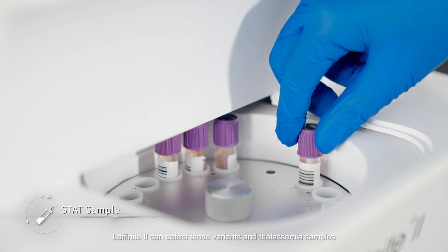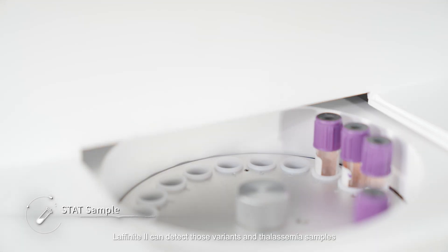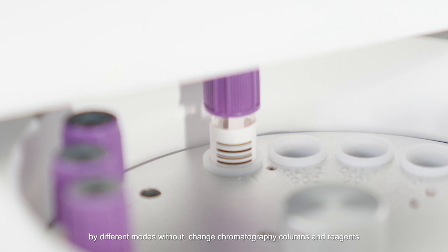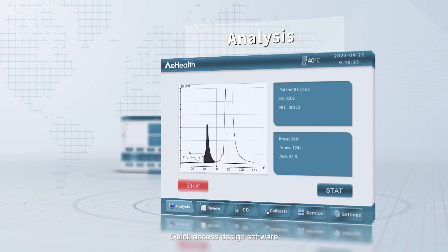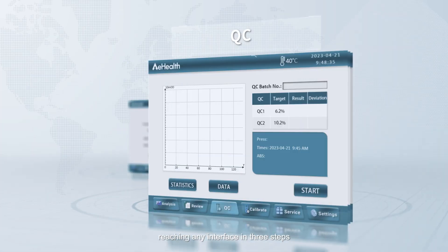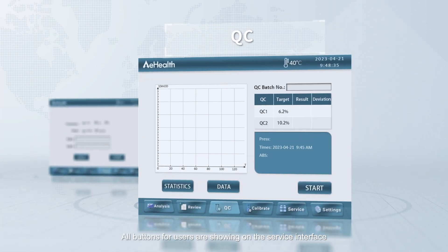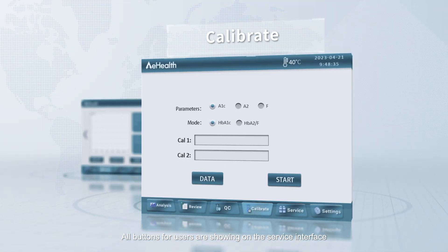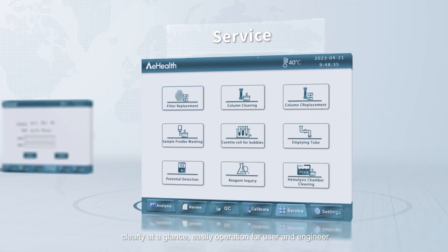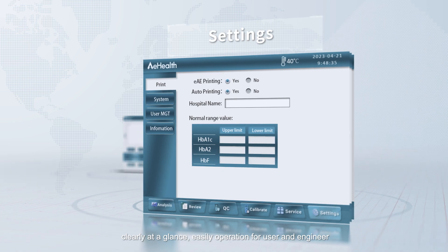LAFINITY-2 can detect those variants and thalassemia samples by different modes without changing chromatography columns and reagents. The quick-access design software navigates any interface in three steps. All buttons for users are shown on the service interface clearly at a glance, enabling easy operation for both users and engineers.